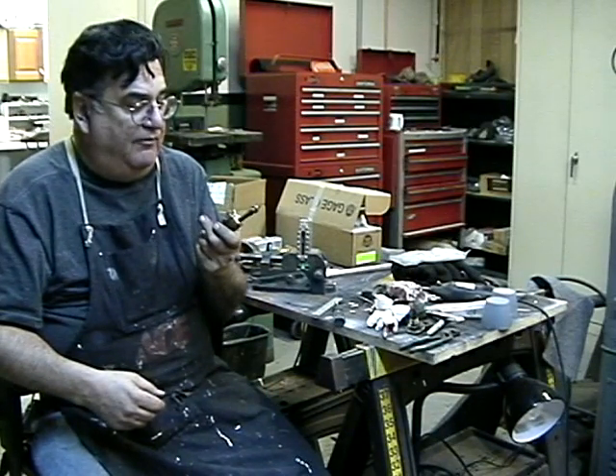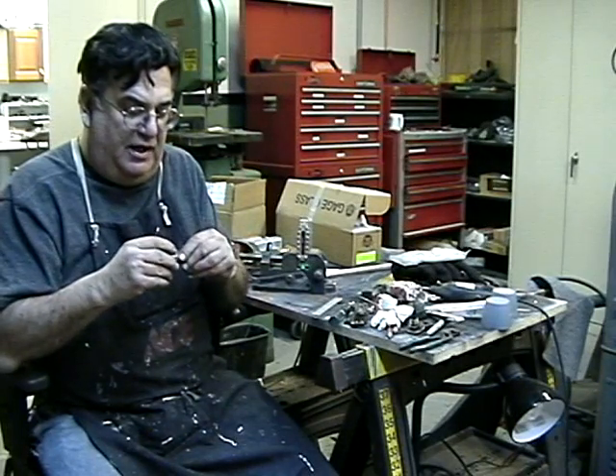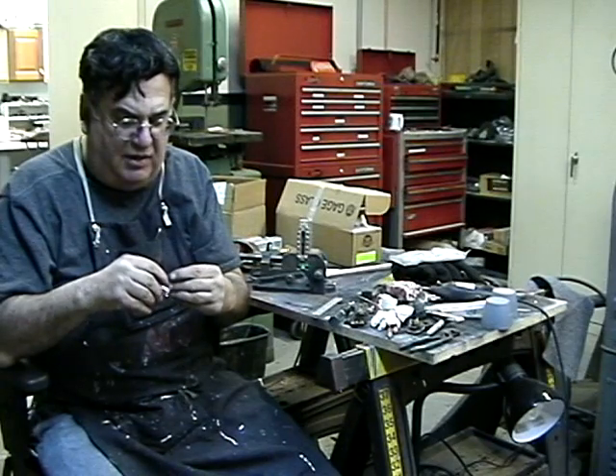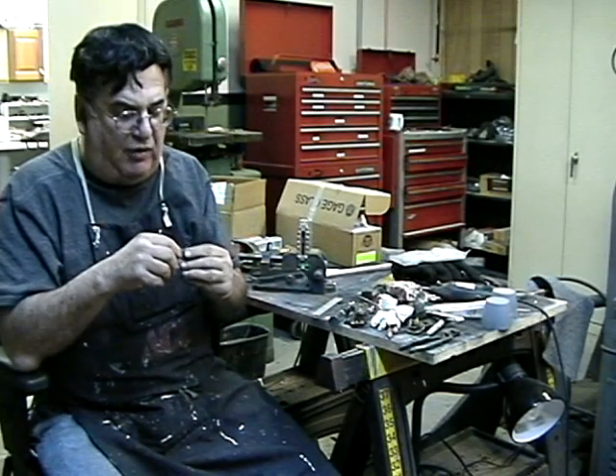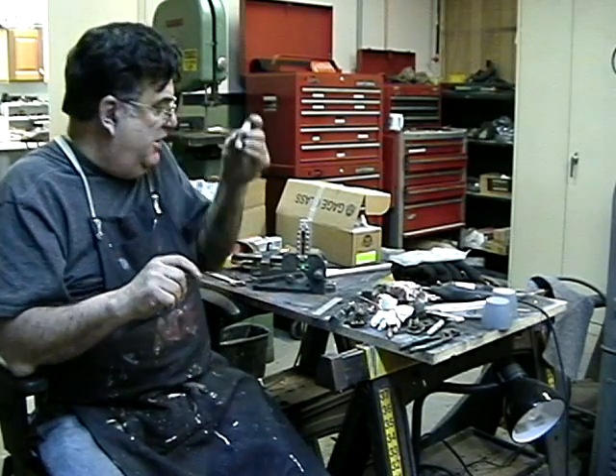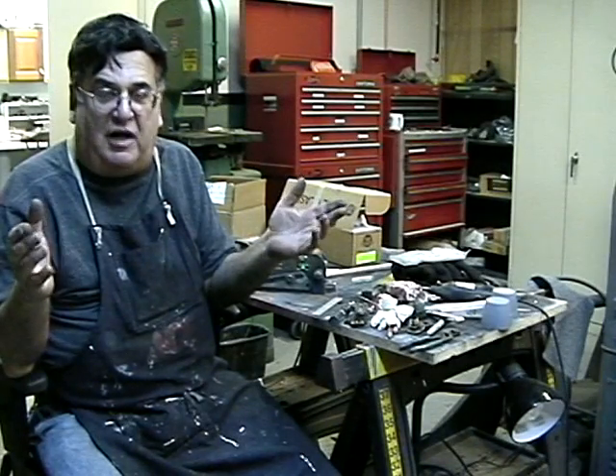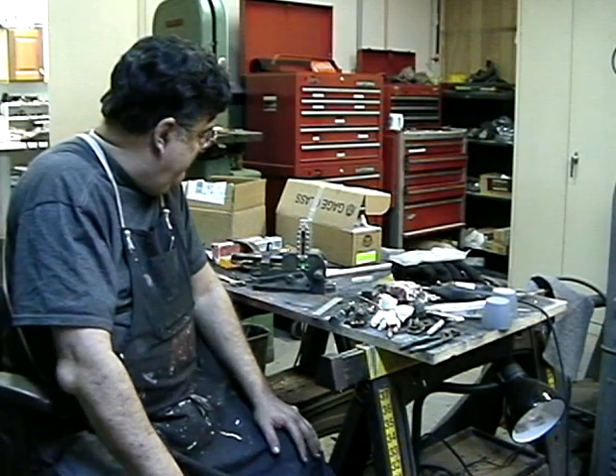I gave the benefit of the doubt to the manufacturer. I tried putting in my own gauge glass and bought extra ones, but they broke on me during installation — they're not completely flat, they have a little bit of a curve, and when you try to tighten them they snap. Also, I don't think the prism in the back is sharp enough — it's more rounded — and it gets a lot of crud in there. The manufacturer paints them red in the back but that only lasts a couple of firings. I even tried high-temperature brake caliper paint and it works for a little bit, then stops working.